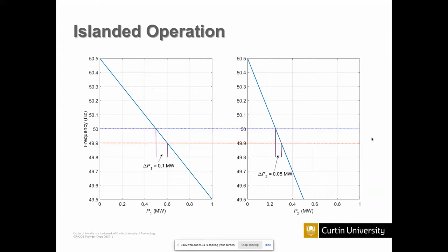The transition from islanded mode and grid connected mode is generally planned. Suppose there is a fault on the other side, what happens is that you just go into islanded mode, and then when the islanded mode finishes, you want to go back to grid connected, grid tied mode. This is a very challenging problem, it's not that easy. But the basic thing is that when you connect an AC source with another AC source, you have to maintain that the phase sequence is same, the voltage is same, and the frequency is same. So direction of rotation same, frequency same, and voltage same. And then you have to connect.